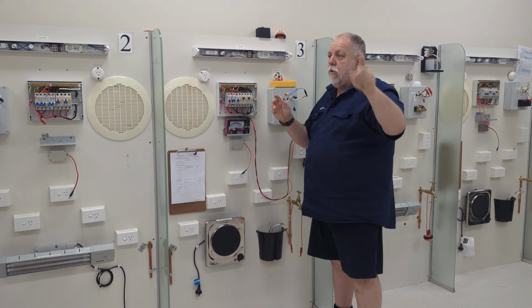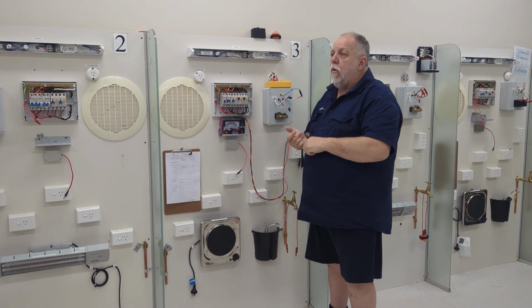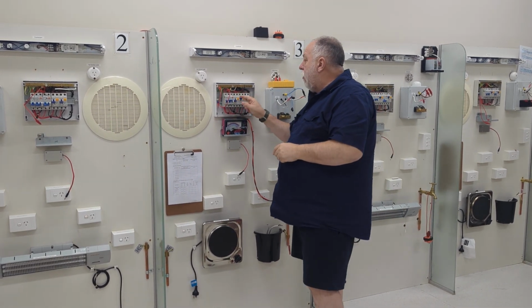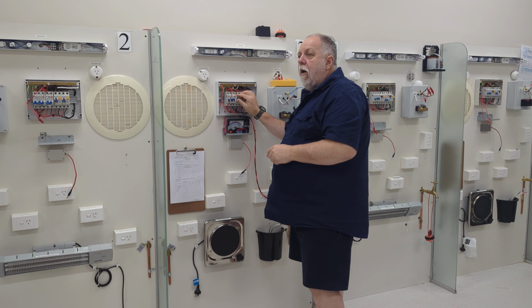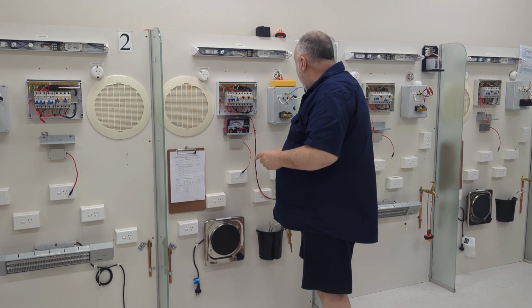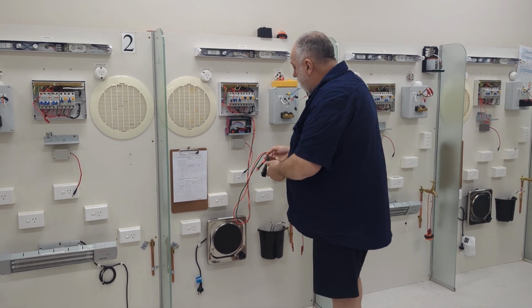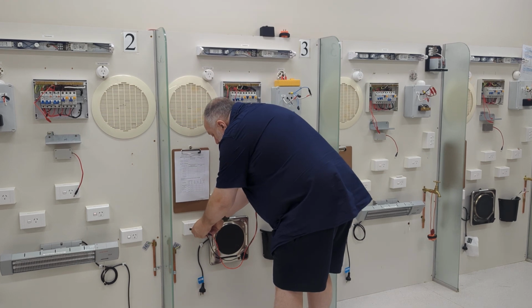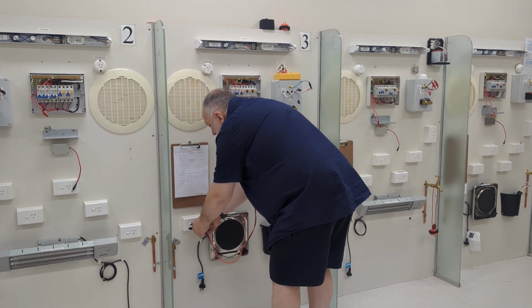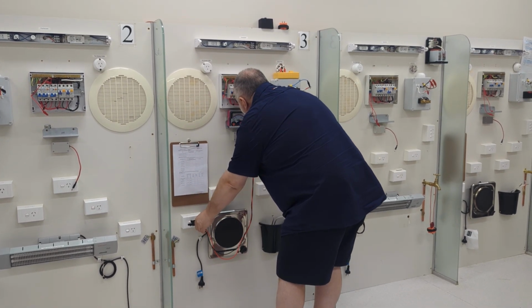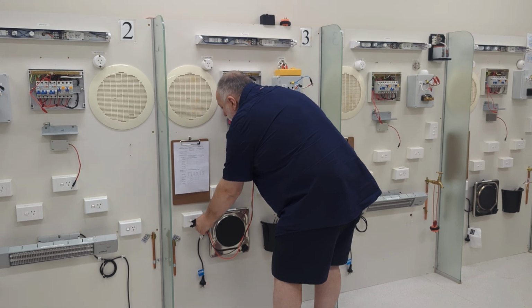You remember it's a closed circuit when we get the weakest point for the circuit breaker to work. If this is too high, it's going to choke the current and not allow it to operate. So what I've done, I've gone to ohms, I come down here, I measure, make sure the switch is turned on, and I've got 0.4 of an ohm.